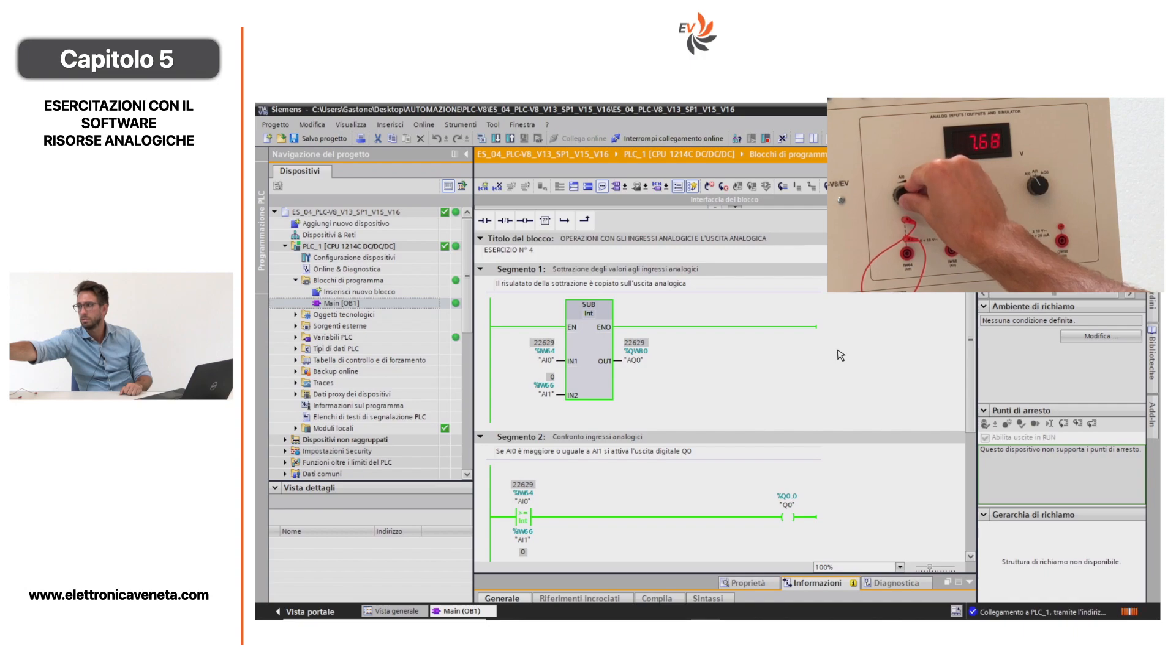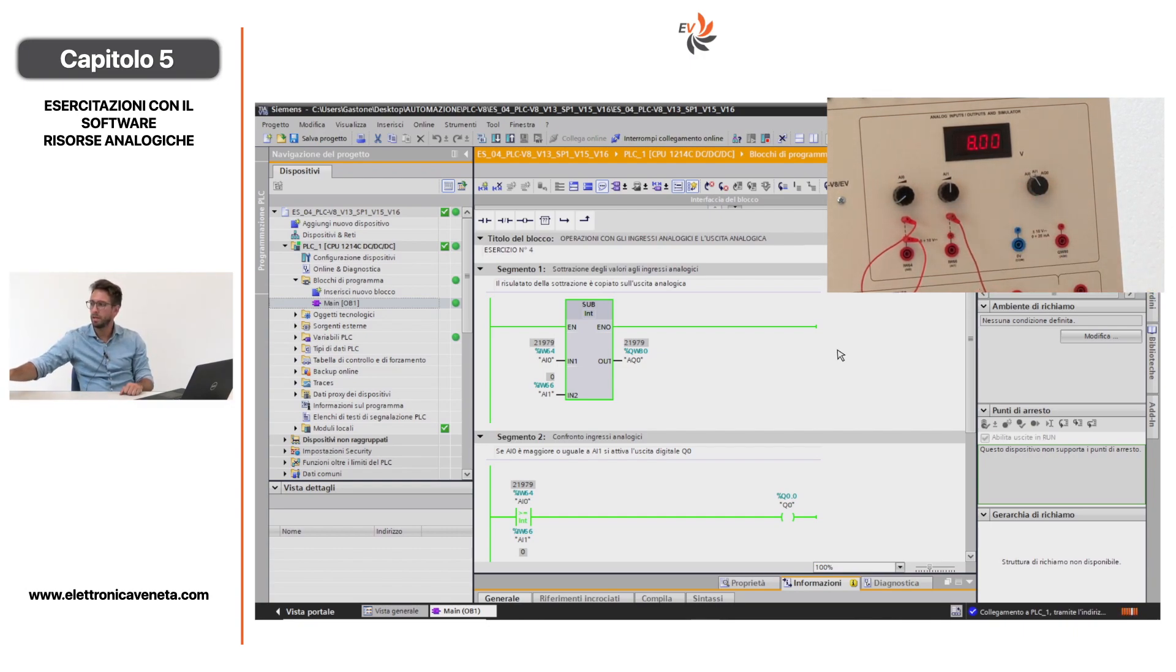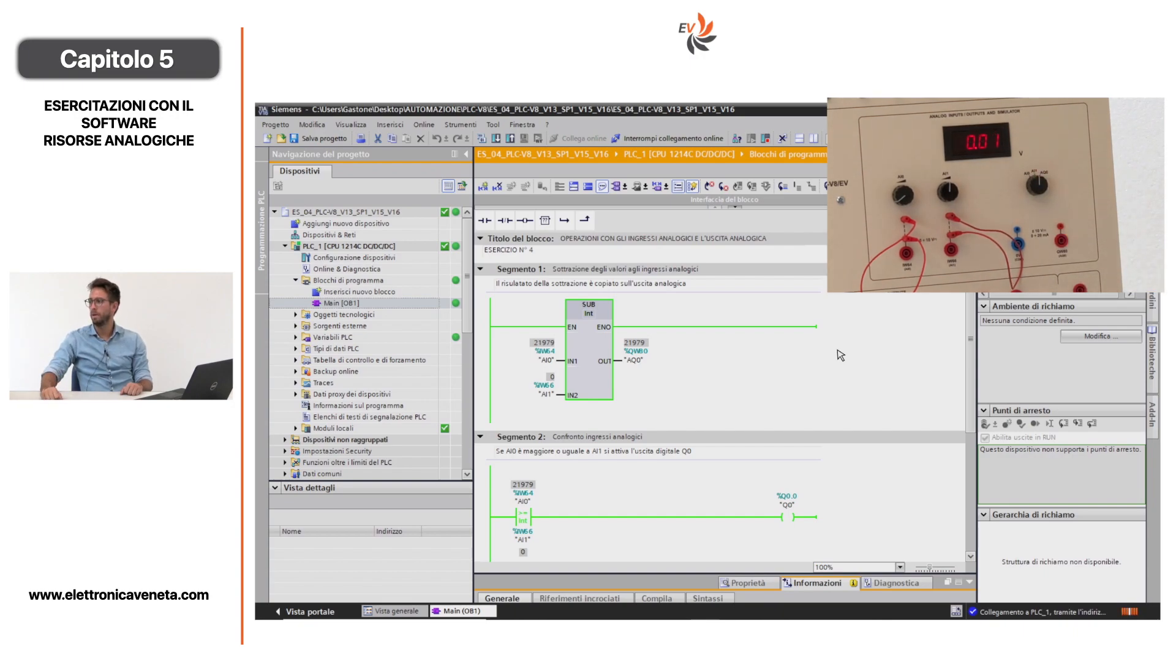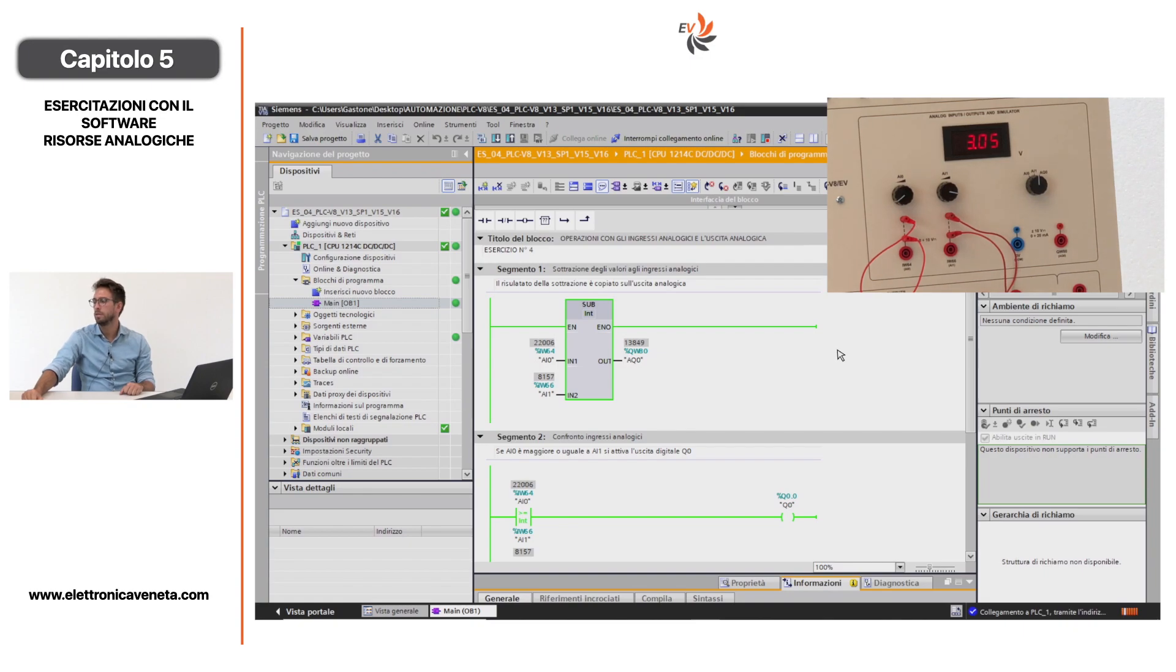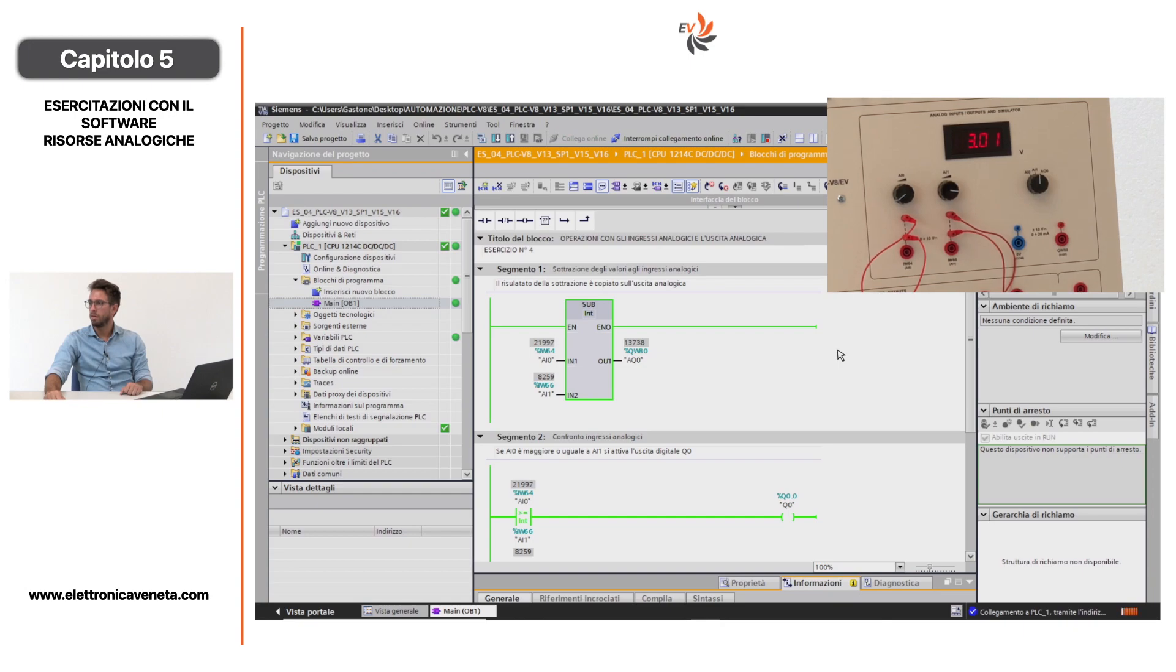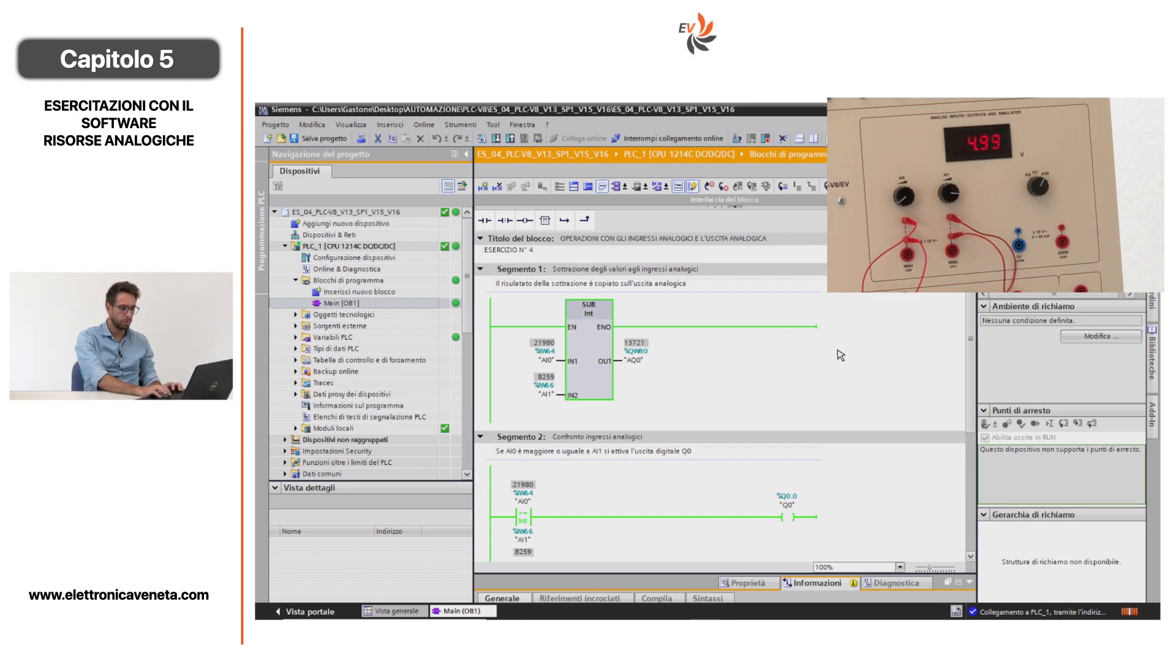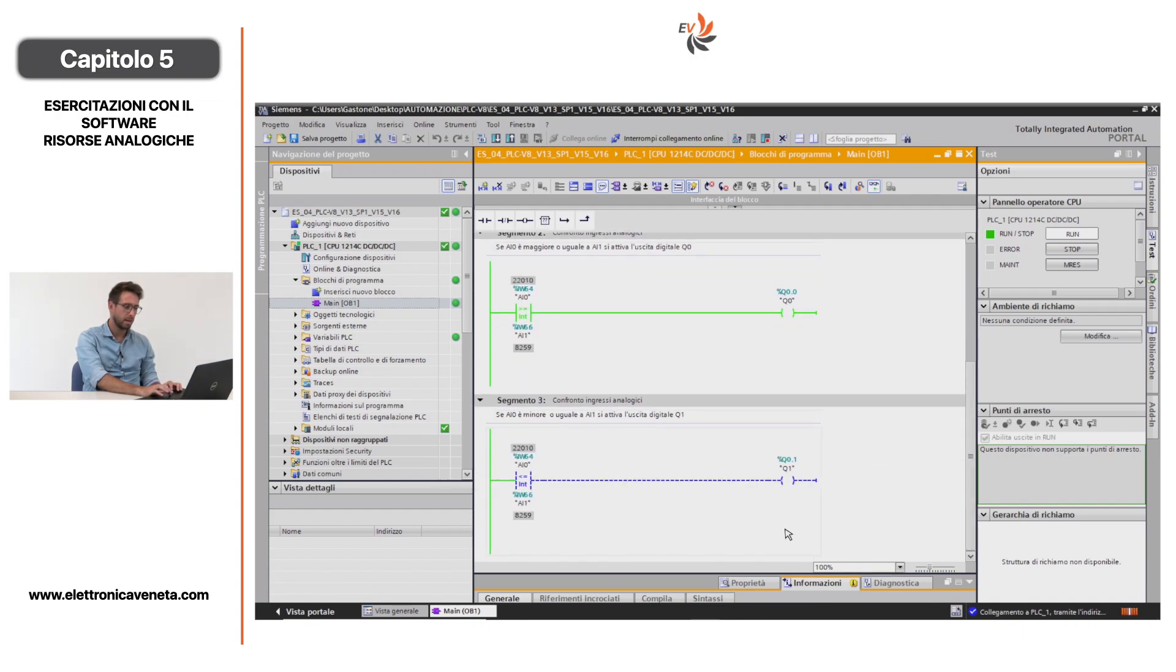Selezionando AI0 nel mio display possiamo settare il nostro ingresso analogico. In questo caso lo poniamo vicino agli 8 volt. Facciamo la stessa operazione per l'ingresso analogico AI1. Selezioniamo AI1 nel mio pannello e modifichiamo l'ingresso, lo portiamo a 3 volt. Quindi selezioniamo AI0, 8 volt meno 3 volt, avremo un valore vicino ai 5 volt in AQ0, che è l'uscita analogica. In questo caso abbiamo che AI0 è maggiore uguale di AI1, 8 è maggiore di 3, quindi si abilita l'uscita digitale Q0.0. Mentre dobbiamo decrementare il valore di AI0 e aumentare il valore di AI1 per avere abilitata l'uscita digitale Q0.1.